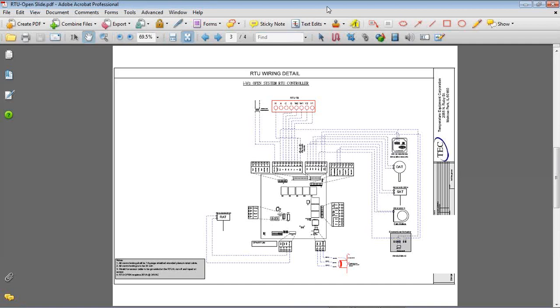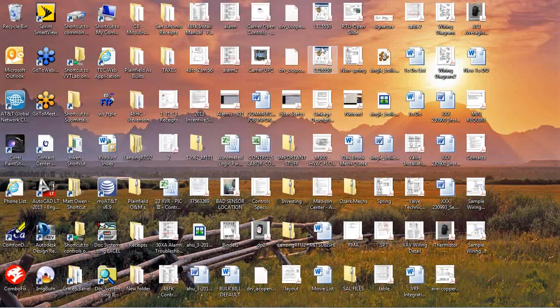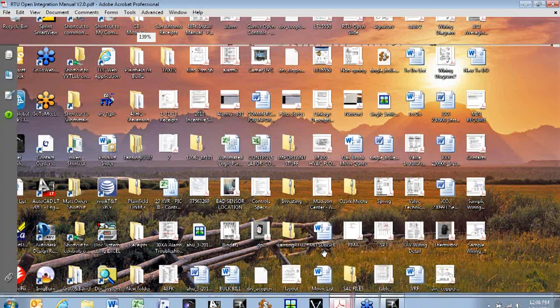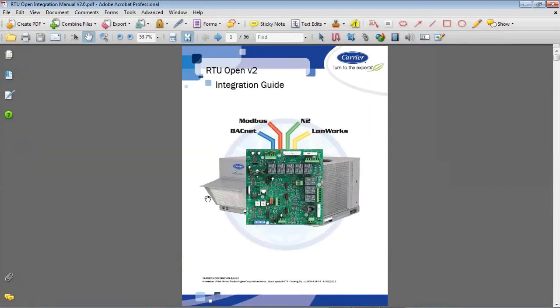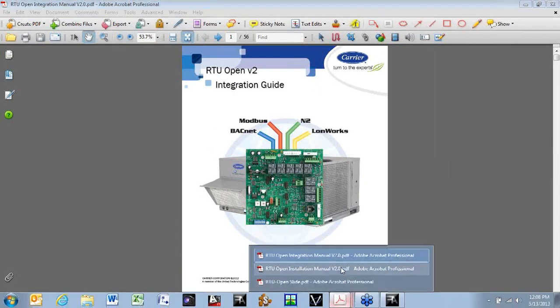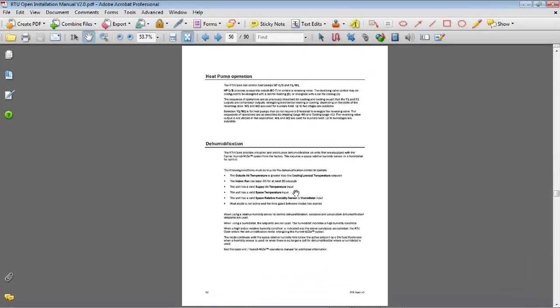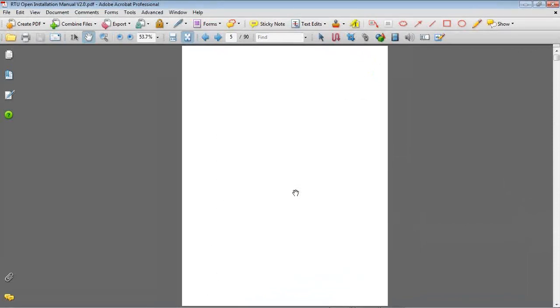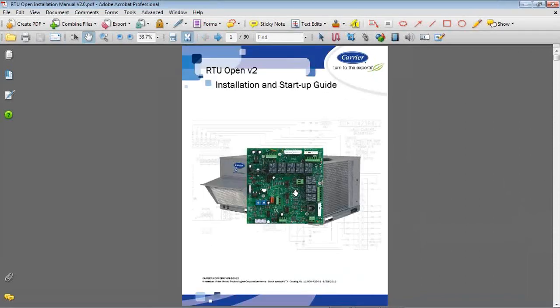So with that, we are going to get into the actual programming of the controller. So I'm going to close this down here real quick. Actually, really quick before that, I'm just going to show you there's two guides for using the RTU Open controller. So we have the RTU Open integration guide, and we also have the RTU Open installation guide. Okay, they're both a little bit different. There's a lot of similarities, but because a lot of these RTU Open boards get integrated into third-party building control systems, we provide a separate manual that has all the installation points and the configuring for setting it up to run with, say, LonWorks or Modbus, something similar to that.